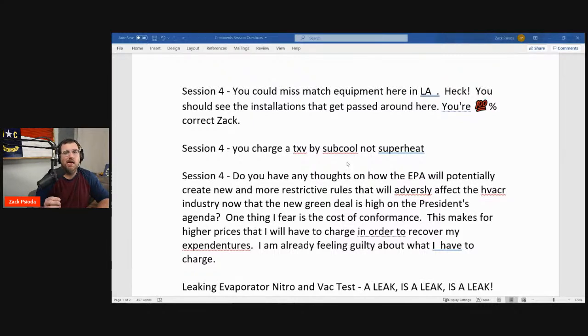For a TXV, it's going to want to keep a certain superheat within parameters. So if it's colder inside, it's going to back that pressure off enough that you still have superheat. So the pressure might be lower than a piston on the suction side because it's trying to keep that superheat up. Now, I'm sort of explaining this here, and hopefully it makes sense. So to get superheat out of refrigerant flow, a TXV is going to have to back off that flow until you have that refrigerant evaporating in the evaporator like it's supposed to do. Because if it's flooding back, it's not evaporating in the evaporator any longer, it's staying in liquid form predominantly. But the TXV is going to back that pressure off until you get a certain amount of superheat coming out.